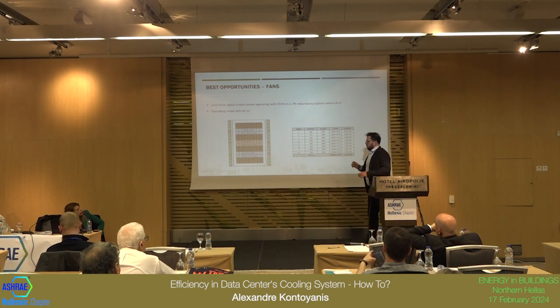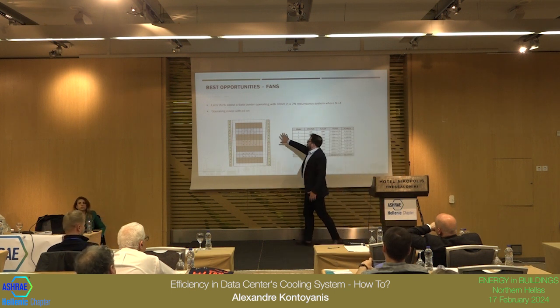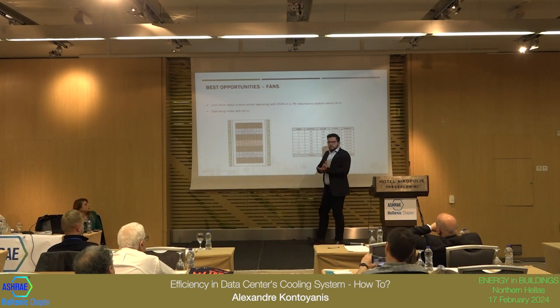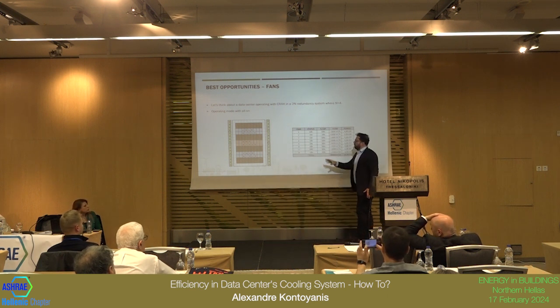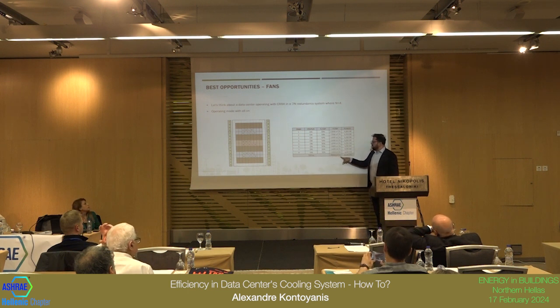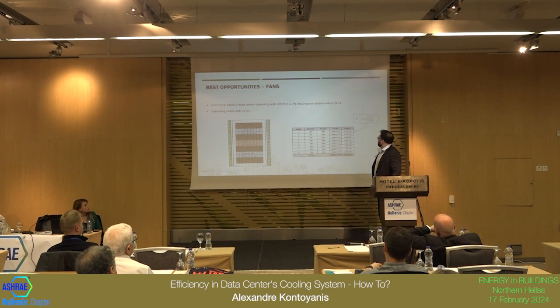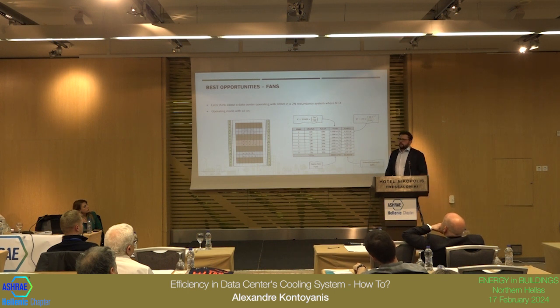If we change this, it's just an operation mode. We turn on all the fans and run them at a speed of 50% each, and we will maintain the same flow. Right? We saw this before. But now, look at the power consumption of this fan. It's 4.06. Of course, now we have 8 turned on. But if you do the maths, same net flow, the potential saving is 60%. Just changing the operation mode.